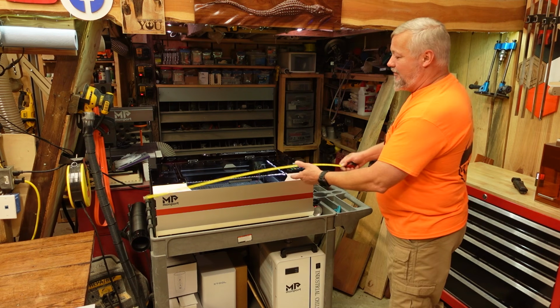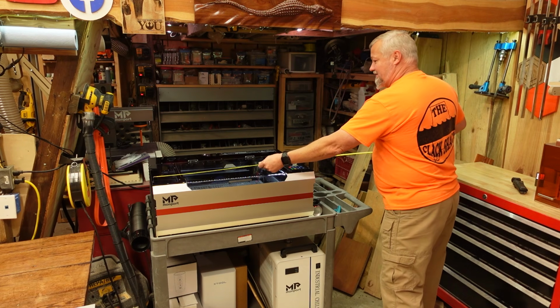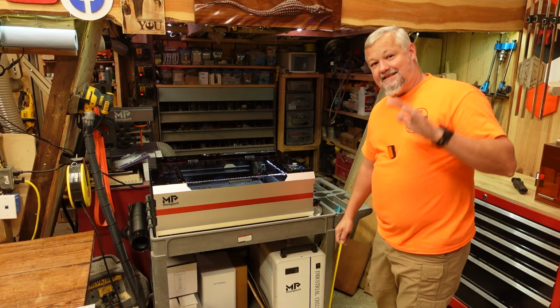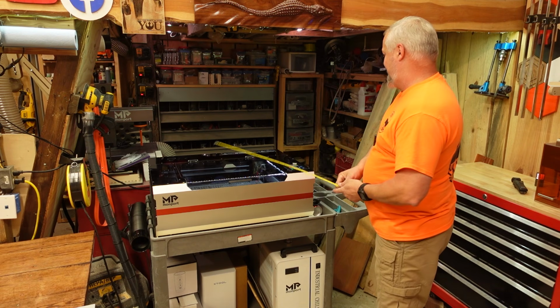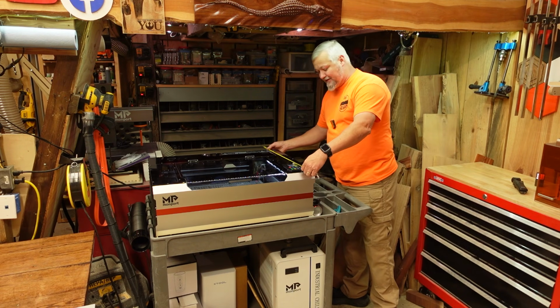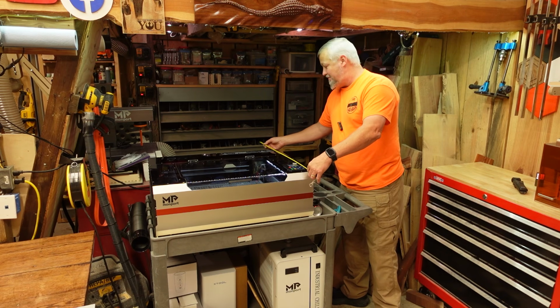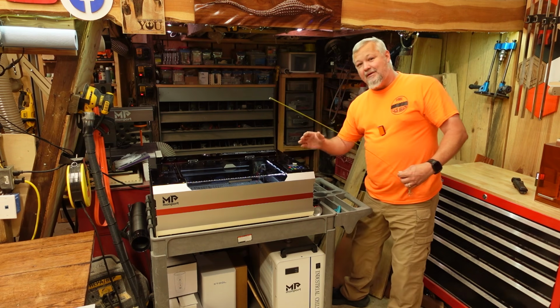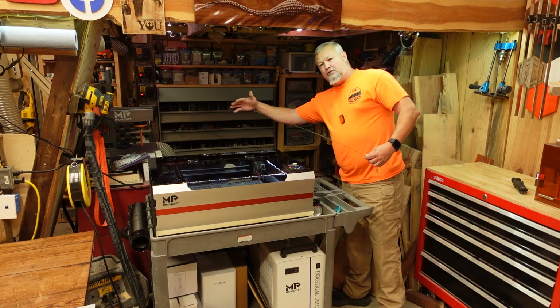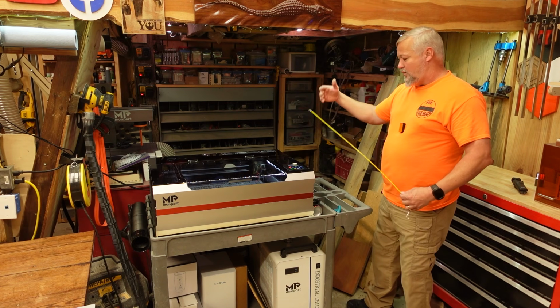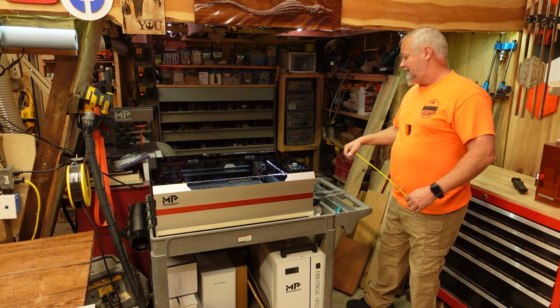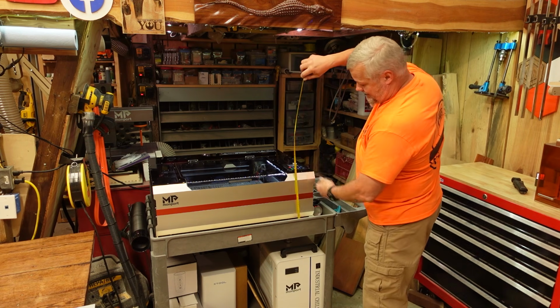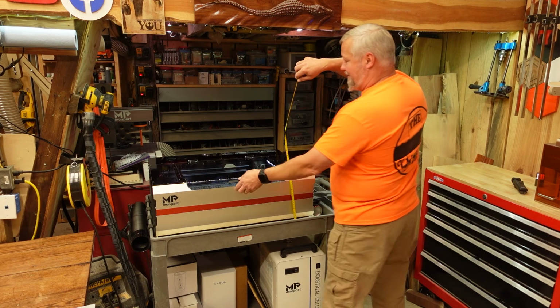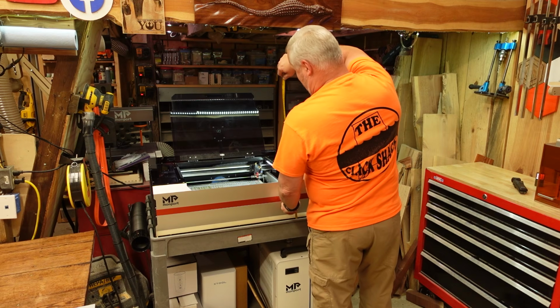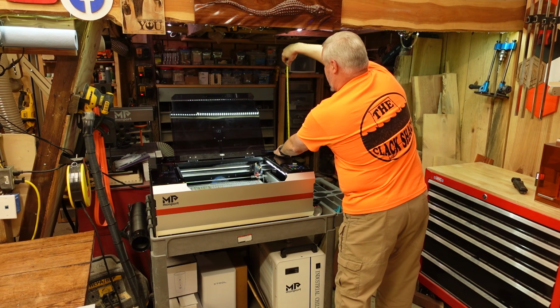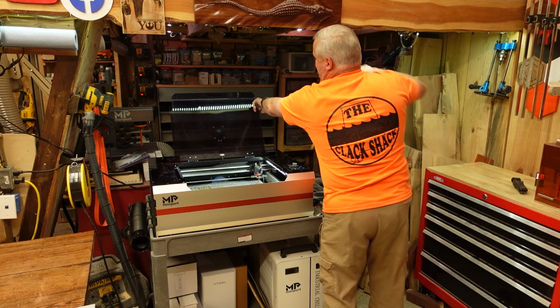It's a little tight, so I would avoid getting that close. Plan on having at least 36 inches to sit it on, but maybe have some area to the sides too. Front to back, including a place for your exhaust, to be on the safe side I'd say at least 32 inches from the front of the machine, giving you room to move that hose around or put an elbow on there. As far as the height of the machine sitting there, it's maybe 12 inches, but you'll need some space over the top, up to about 28 inches, to be able to open the door.